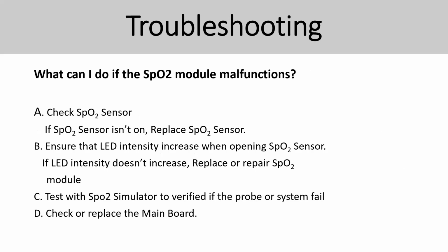For SpO2 module malfunction, normally you're going to check the SpO2 sensor. If the SpO2 sensor is not on, meaning you cannot see the red light, replace the sensor. This is one of the very common problems that you're going to see in SpO2. Another way is to use the SpO2 simulator to verify whether the probe is working properly or not. If the probe is working, or you replace it with another probe and the patient monitor still cannot capture the SpO2, that means something is wrong with the SpO2 board or the main board.